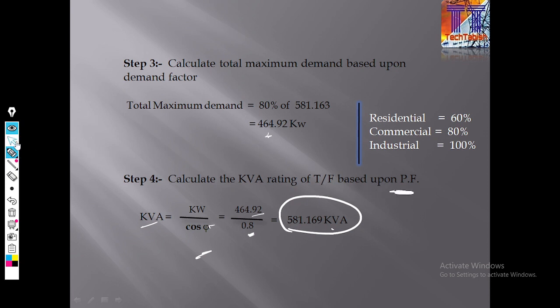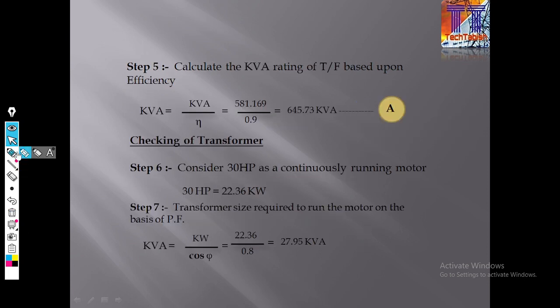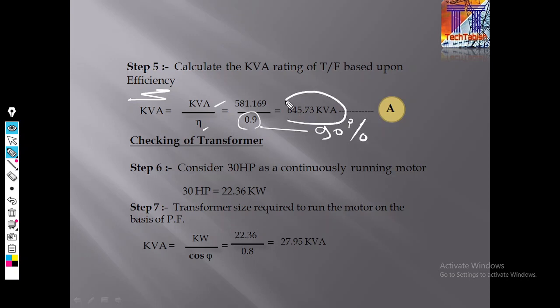So in the next slide we will see the kVA rating based upon efficiency. Okay, if we talk about efficiency, then kVA upon efficiency, which is 0.9. So the transformer efficiency is almost 90%. Okay, if we divide this, then we will get 645.73 kVA. We have denoted this with A. Okay, now in the next slide we will come to the checking of the transformer.